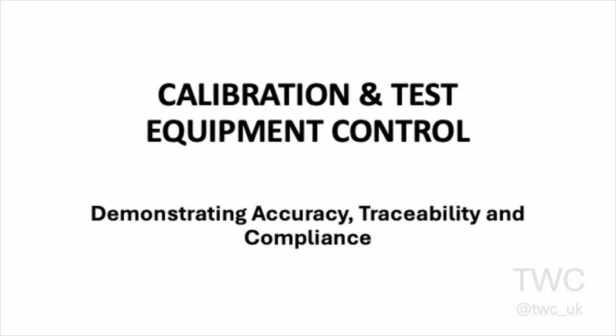In this video we're looking at calibration and test equipment control. Assessors are not only interested in the results recorded on installation paperwork, they also want confidence that those results were obtained using suitable equipment that is properly controlled, maintained and traceable. Good calibration management is about much more than holding a certificate. It involves equipment control, traceability, record keeping and confidence in the measurements that support compliance.